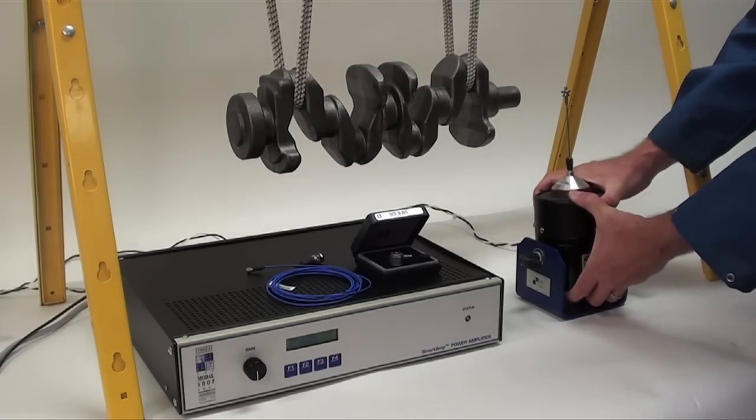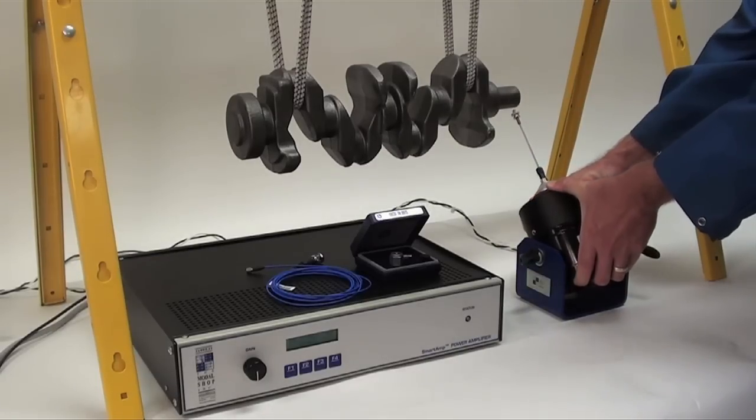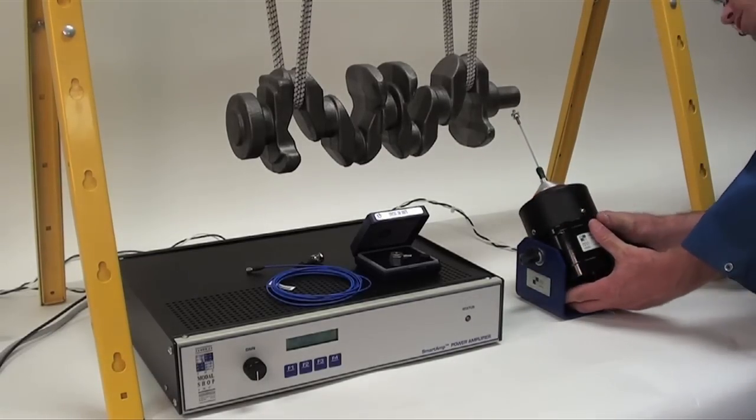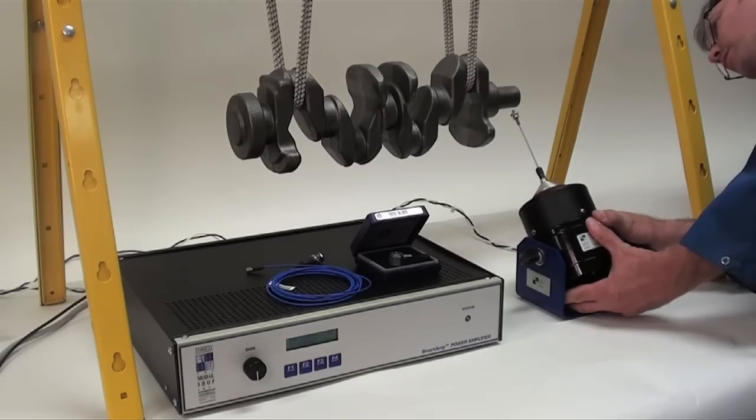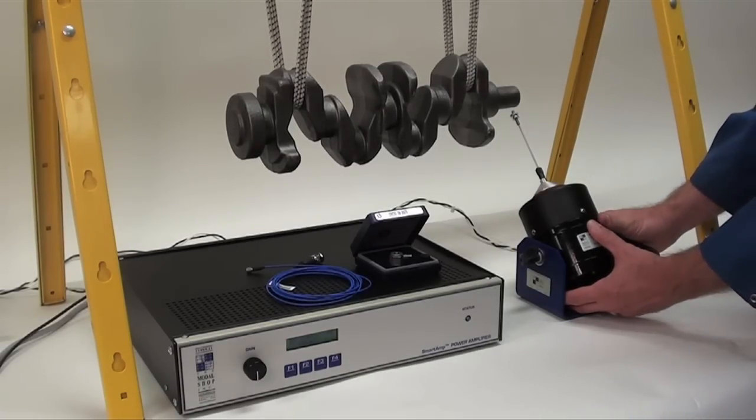And we'll adjust the shaker body in the trunnion such that we'll be exciting at about a 45 degree angle so that we can get both a horizontal and a vertical input.